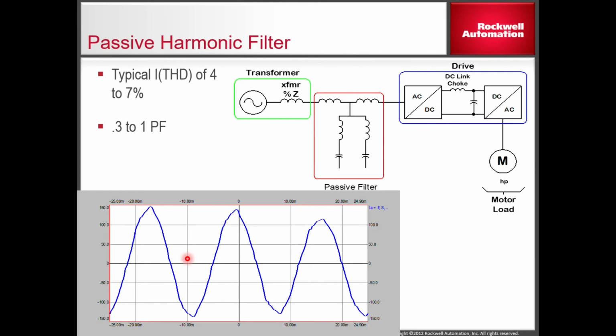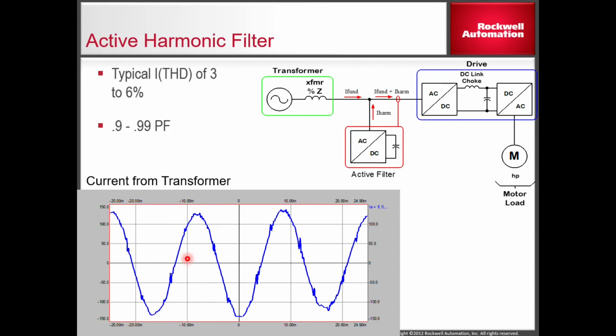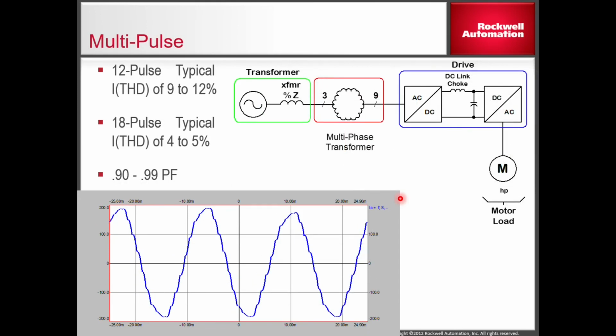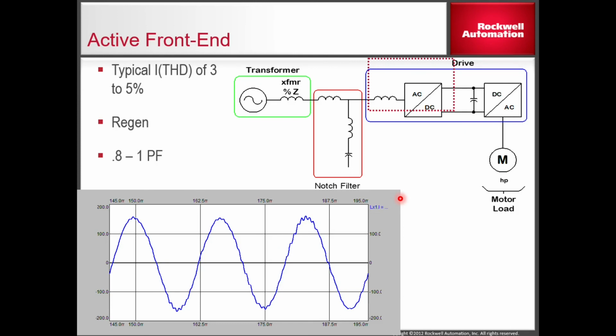If you put a passive harmonic filter on, we can go down to about 4 to 7%. And it has a reactor built into it, so you don't have to add a reactor as well. Then the active harmonic filter, which again acts like noise-canceling headphones, can get you 3 to 6%. Multi-pulse front ends, depending on whether it's 12 or 18, can get you down to 4 to 5%. And then the active front end, which again is like the active harmonic filter, down to 3 to 5%.